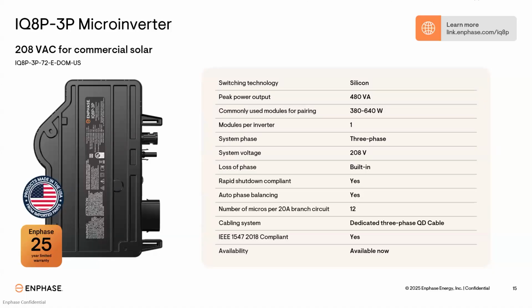Has the same cool stuff as the other microinverter. Built-in loss of phase, rapid shutdown compliant, auto phase balancing. Big difference though, you can only put 12 of these per 20 amp branch circuit. And that is due to the voltage and amperage differences between those two microinverters. But again, still same cool stuff, made in USA and a 25-year warranty.